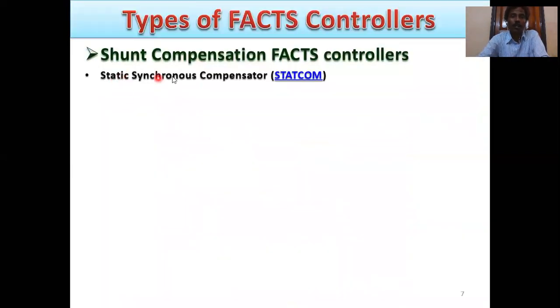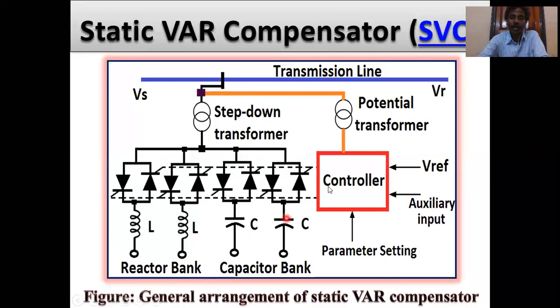So shunt compensation: static synchronous compensator, STATCOM, and static var compensator. This is the configuration of the static var compensator. This is the reactor bank. This is the capacitor bank. This is the controller, step down transformer, and transmission line. This is the transmission line.